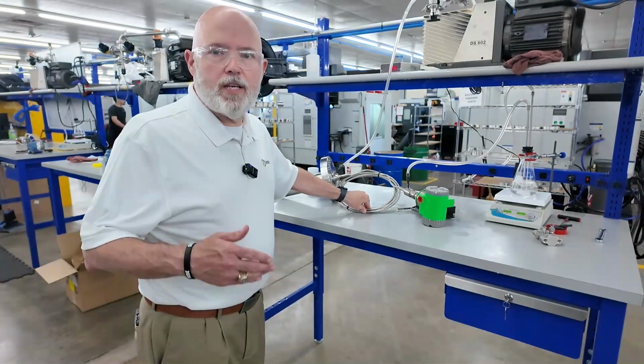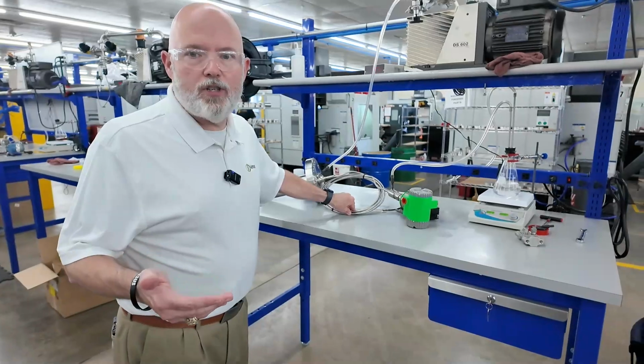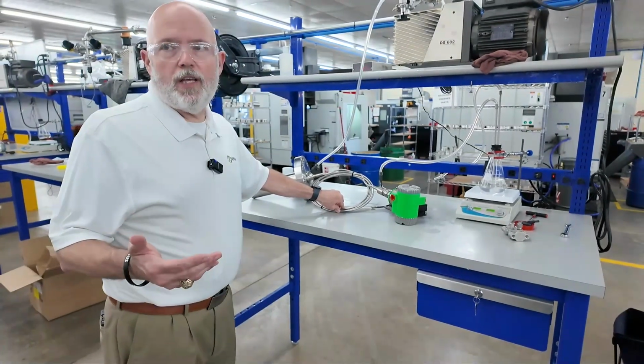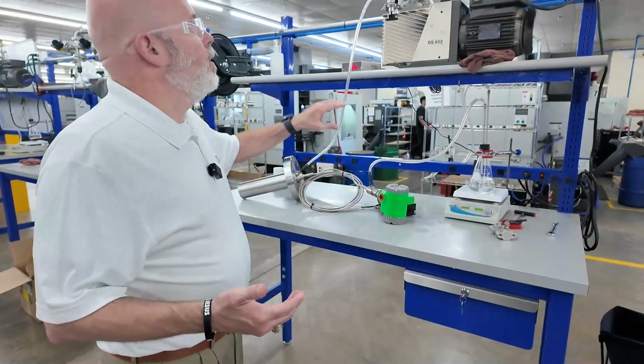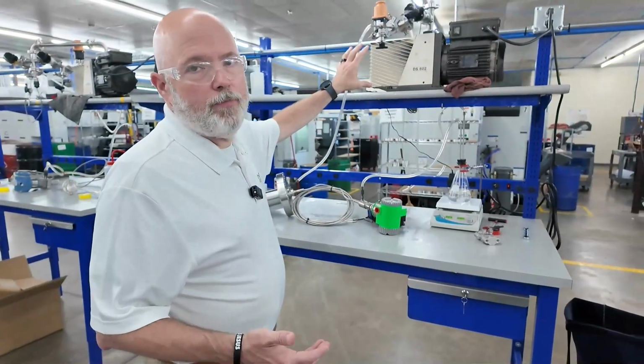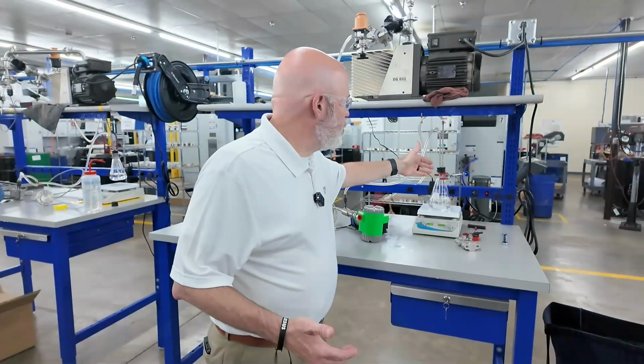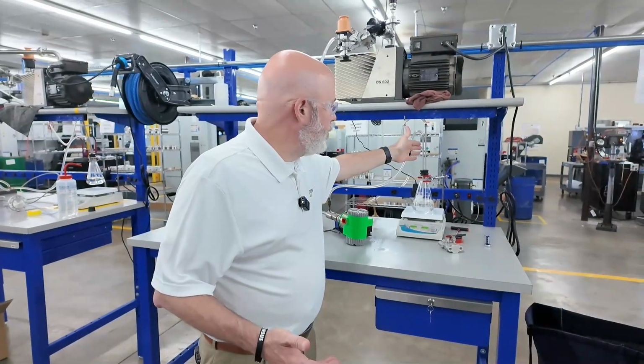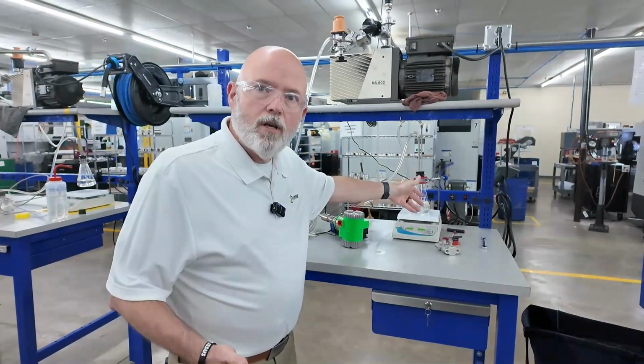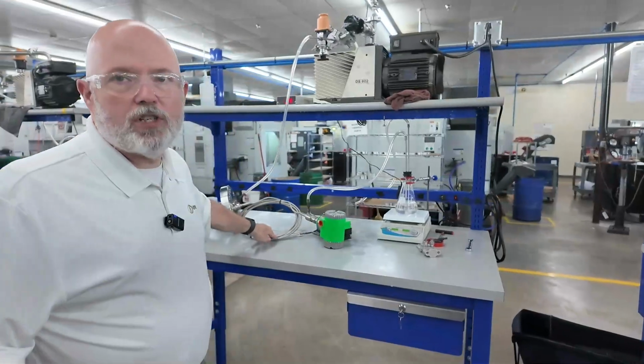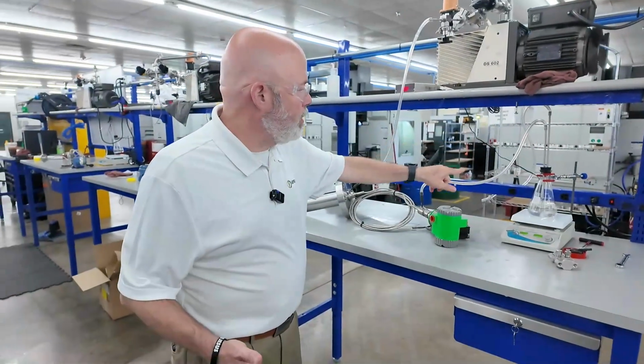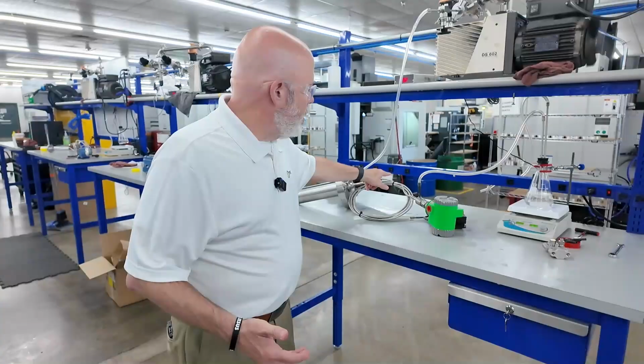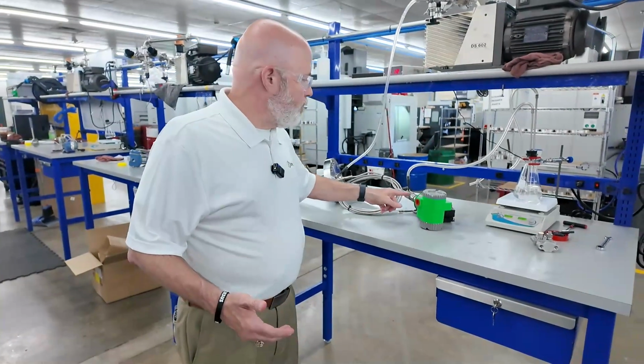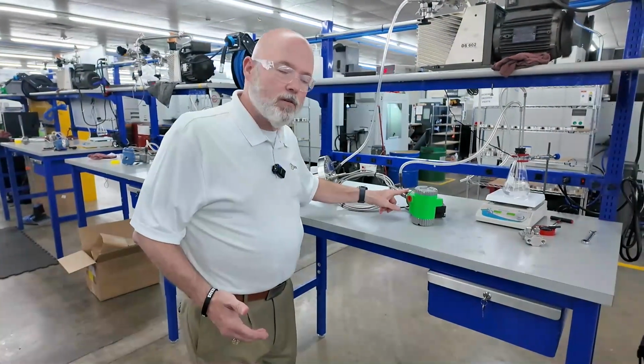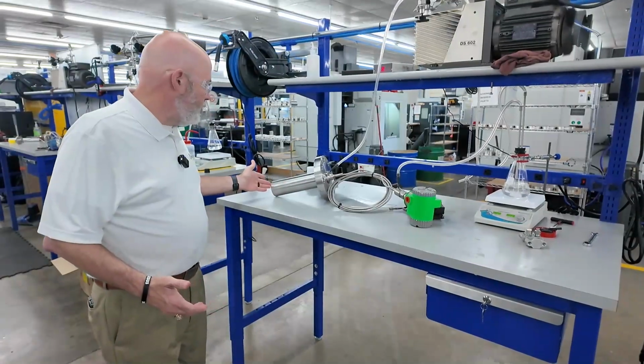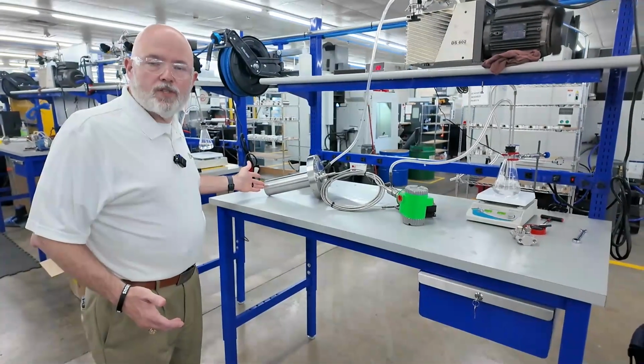Once the system has undergone the prescribed amount of evacuation, we fill it—a very simple process. We turn off the vacuum, then simply drop the fill tube down into the fluid, and the negative pressure in the system pulls that fill fluid through the tubing and into the system, all the way from the sensor on the transmitter to the back side of the diaphragm on the extended seal.